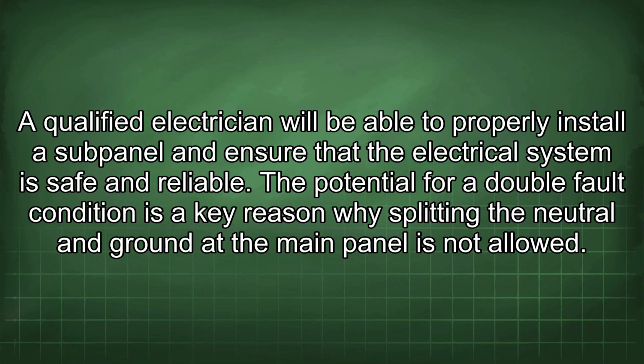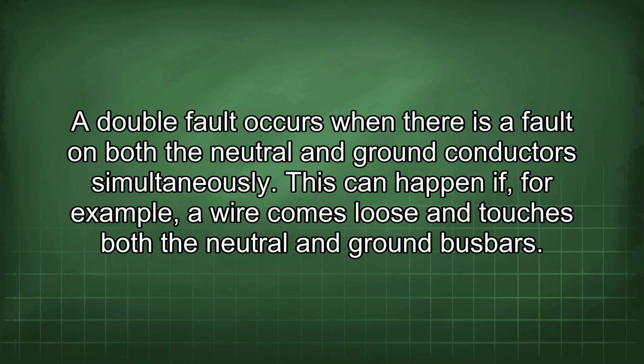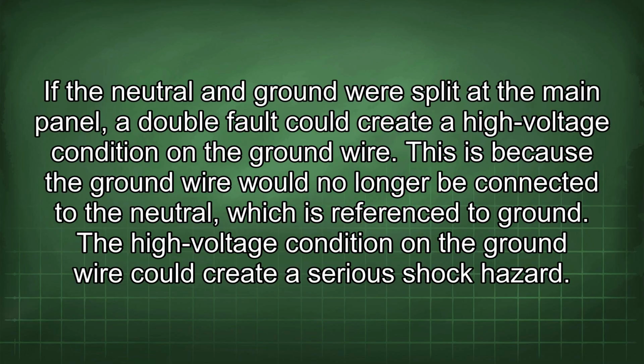reliable. The potential for a double fault condition is a key reason why splitting the neutral and ground at the main panel is not allowed. A double fault occurs when there is a fault on both the neutral and ground conductors simultaneously. This can happen if, for example, a wire comes loose and touches both the neutral and ground bus bars.